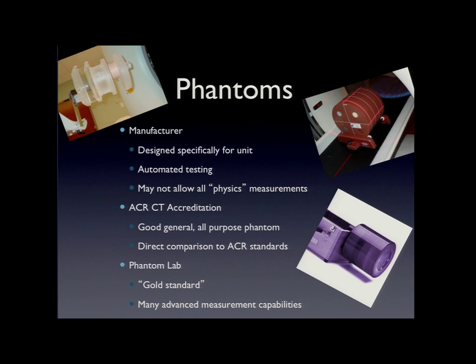Of course, the ACR CT Phantom is widely used because a lot of people that use clinical CT are accredited by the ACR. Since they're going to be submitting them every 3 years, let's just continue to monitor that through the year. Just say, okay, you're still within these specs for the ACR and such. And so we can just keep comparing that and make sure we're adhering to that.